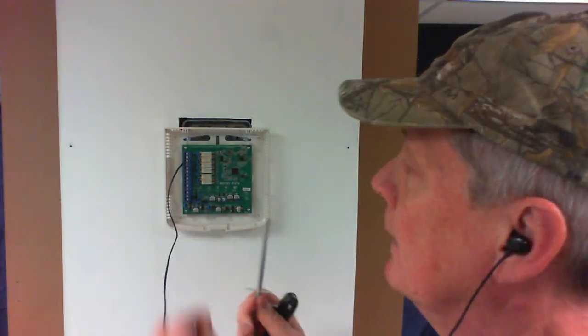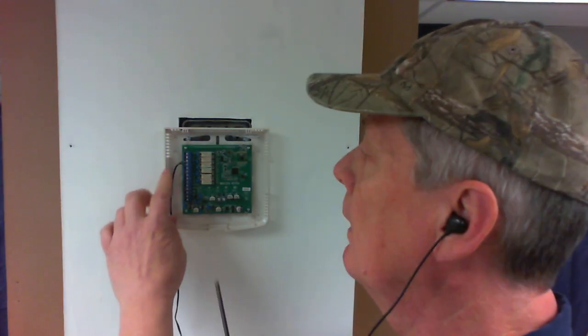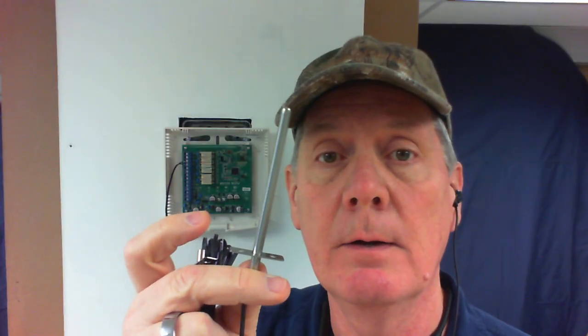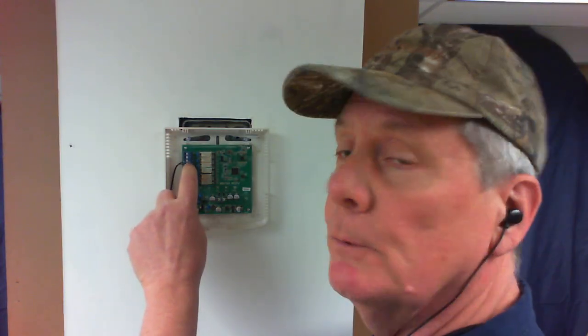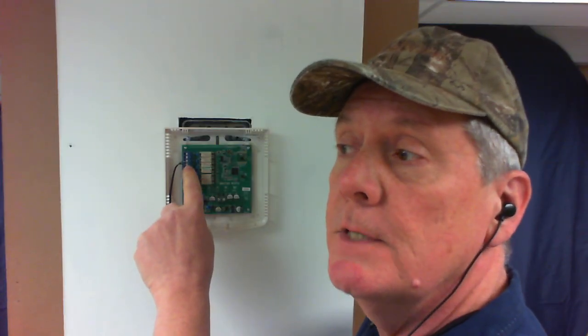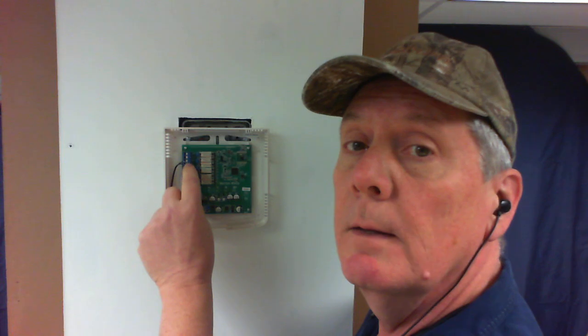If you do not install it, then your thermostat is going to constantly give you an error message on the screen indicating that the plenum sensor is missing, plenum sensor loss issue. So you must connect it. The control board is looking for this input from this sensor. And what this is, it's a temperature sensor. It's a thermal resistor, or a thermistor, it's called. So the resistance value changes based on temperature. Nominally, this is a 10,000 ohm resistor or thermistor. So this control module is looking for something in the neighborhood of 10,000 ohms between the P1 and P2 terminals.